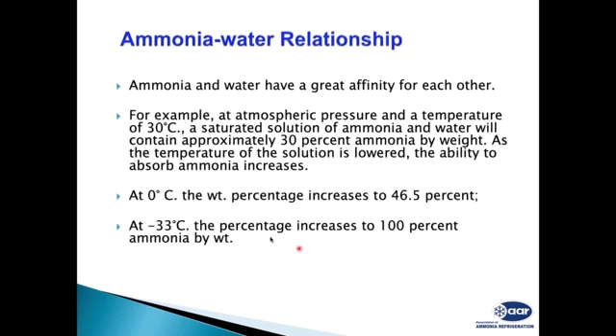At atmospheric pressure and 30 degrees centigrade, a saturated solution of ammonia and water will contain 30% ammonia. It means in water we can have 30% ammonia mixing at 30 degrees centigrade. If we go to 0 degrees centigrade, which is typical of positive cold storage applications, the ammonia solubility goes to 46%. And if you go to -33, which is our freezing and cold storage temperature, the solubility of ammonia in water is 100%. When ammonia and water mix, it becomes an aqueous ammonia solution.